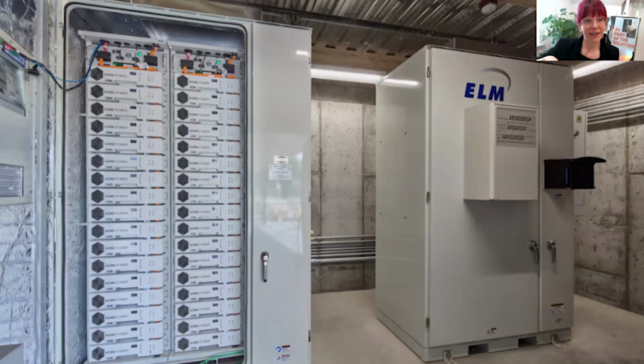That rack relays all of that information to what's called a master BMS, controlled by the building automation system. That's a single point of control for multiple racks in a bank. It has a web-based human machine interface, HMI, for troubleshooting and configuration, and this is done off-site.